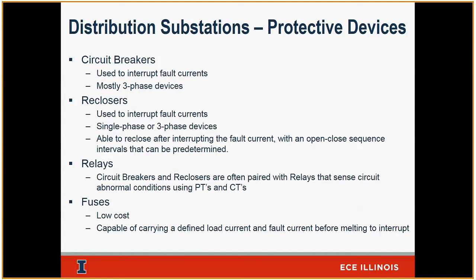A relay, really, you can think of as the brains of the circuit breaker or the recloser, the eyes and the brains, right? So it's got the measuring devices going into it, the CTs and the PTs, current transformers, which give you the current magnitude, and voltage transformers, which give you the voltage magnitudes coming off each of these lines. So if I have a circuit breaker here, I know the current and the voltage most likely on both sides of me. So I know the current upstream and downstream, and I know the voltage upstream and downstream, and that's being fed to a relay. Small box. In today's world, they're all microprocessor-based, so they're all small computers, right? And that information comes in. It's digital to you, and you as an engineer can program it.